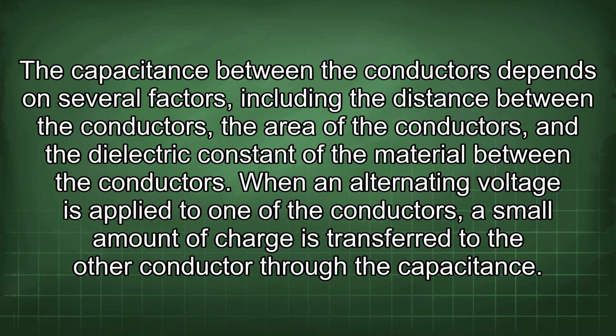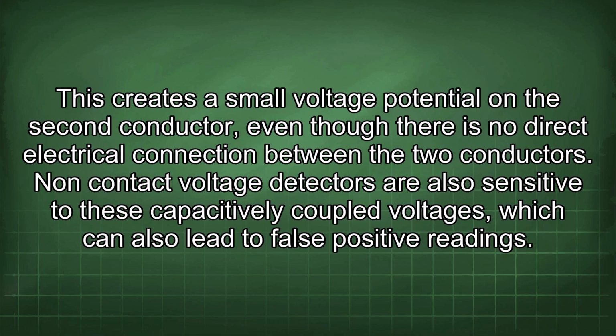When an alternating voltage is applied to one of the conductors, a small amount of charge is transferred to the other conductor through the capacitance. This creates a small voltage potential on the second conductor, even though there is no direct electrical connection between the two conductors. Non-contact voltage detectors are also sensitive to these capacitively coupled voltages, which can also lead to false positive readings.